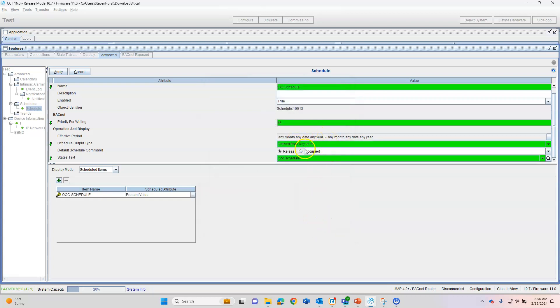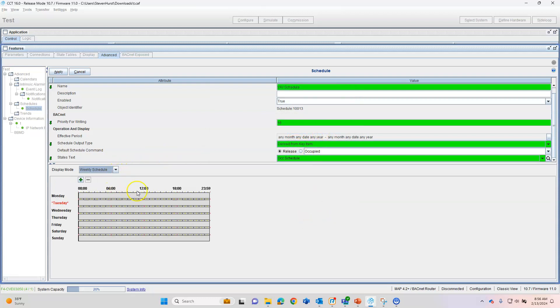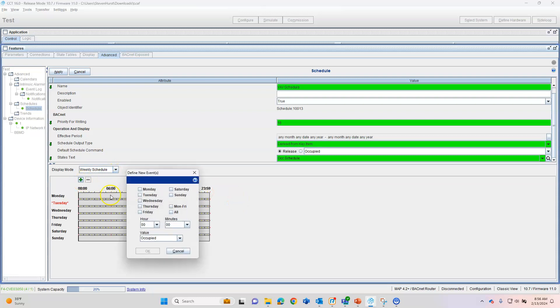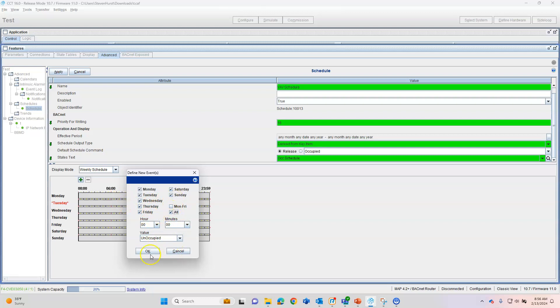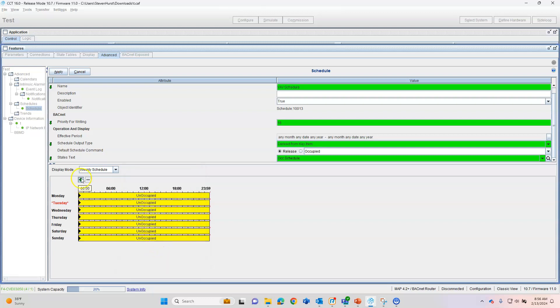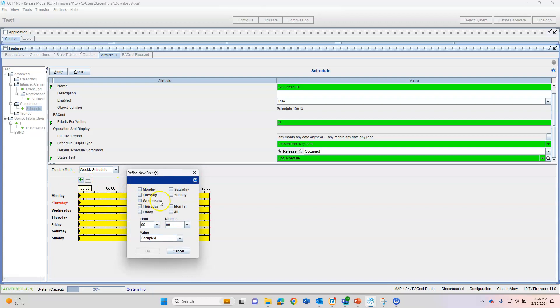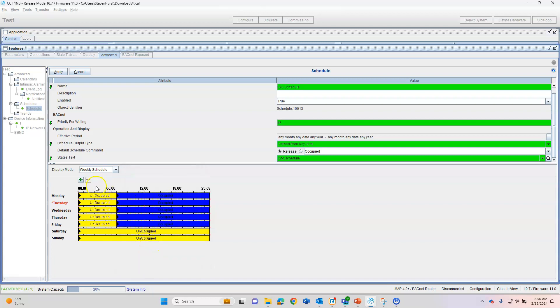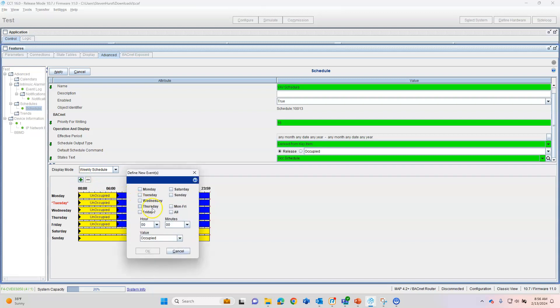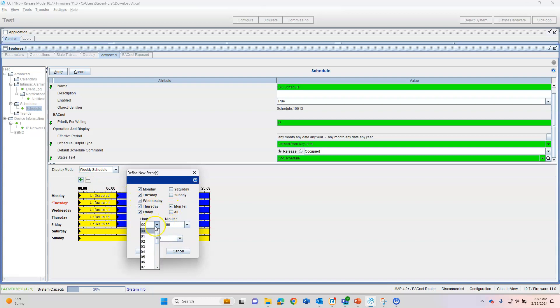It'll auto-populate this for us here. So I can now go to weekly schedule, click on that plus button, and I'll just start out with unoccupied all the way around. Then I'll throw in an occupied, let's say Monday through Friday from seven to five. So here's our seven, and we're going to go Monday through Friday, unoccupied again at five, which is 1700 hours.